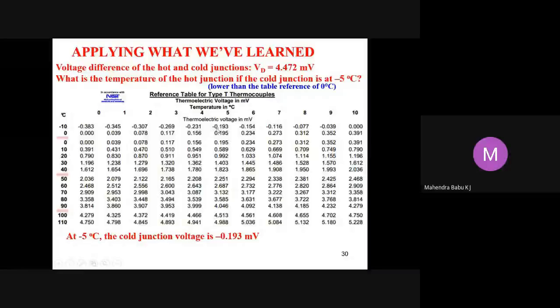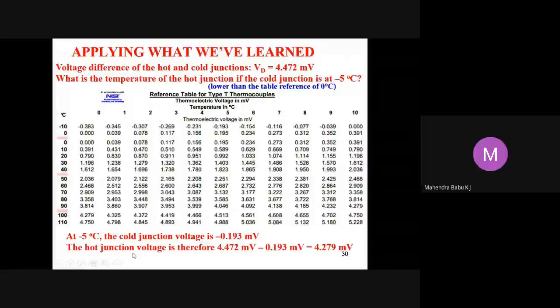So at minus 5, the millivolt reading is minus 0.193 millivolts. That is the cold junction voltage. The hot junction voltage is therefore 4.472 minus 0.193 millivolts, which comes to 4.279 millivolts again. The temperature corresponding to this 4.279 millivolts, you can take this or this, both will give 100 degrees Celsius. Like this, one can find the hot junction temperature, knowing the difference in voltage reading between the hot and cold junction and the cold junction temperature.